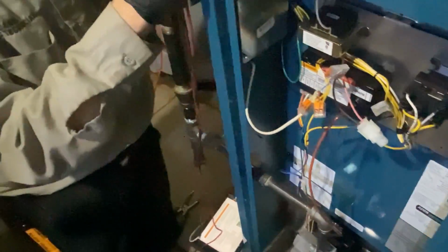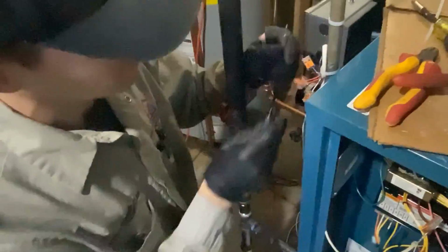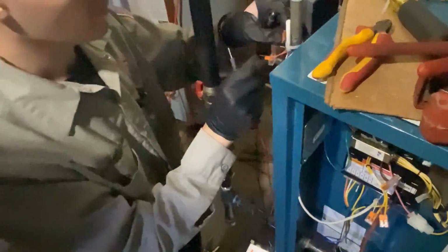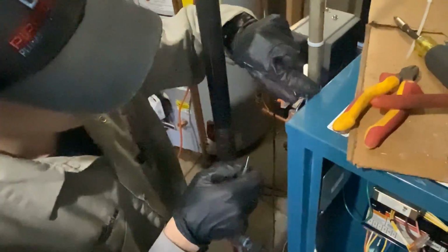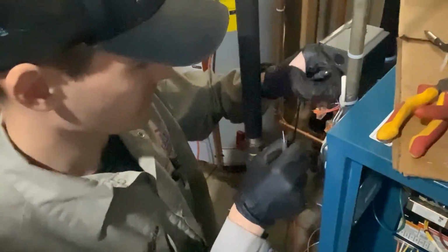All right, so one issue that we're running into right now is our Ecobee thermostat is not getting voltage or not turning on. It's not spreading its wings, so we're going to confirm which one of these yellow wires is actually 24 volts. So we're going to take our voltmeter lead to that, and 24 on R. 24 on R. Now I just reversed it, by the way, and our white nothing should be there, but let's check that anyway. And nothing there. Good. So between R and blue, we should have 24 volts. So we'll take the black off there, the red to blue, and we have 2 volts. Nope, 24. There you go. See?